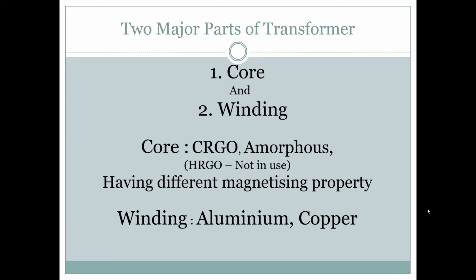Now aluminium conductivity is less than copper, but if we increase the surface area, then what happens? We get the same condition. So aluminium foil is now being tried, and it is very, very successful. Now in the distribution sector, I'm not talking about large transformers. In distribution, up to 5, 7 MVA and 10 MVA station transformers, we have gone for aluminium foil. Now copper foil has also come. It is the next generation, but aluminium foil has been standardized.